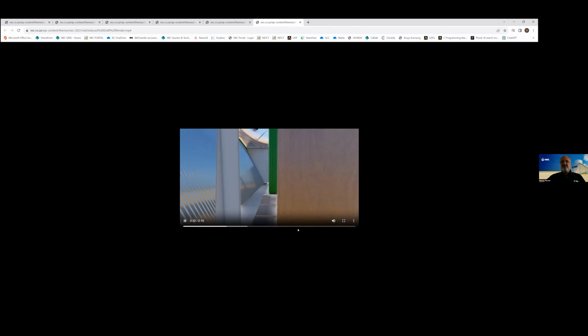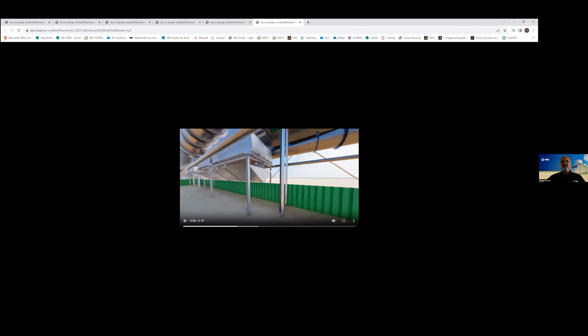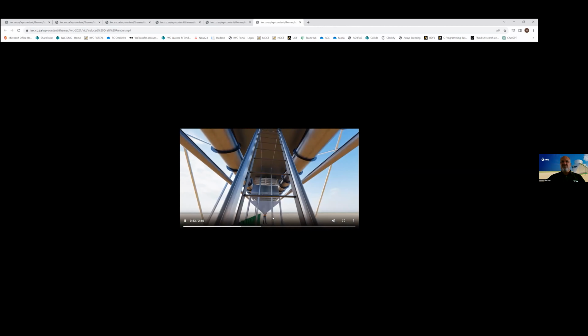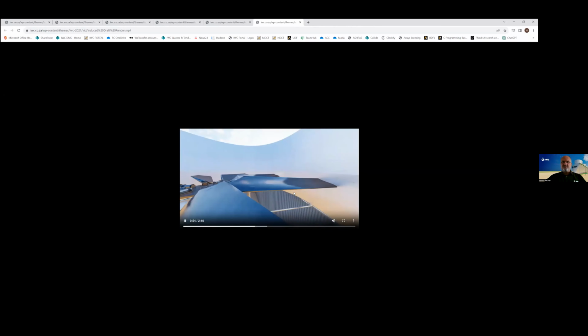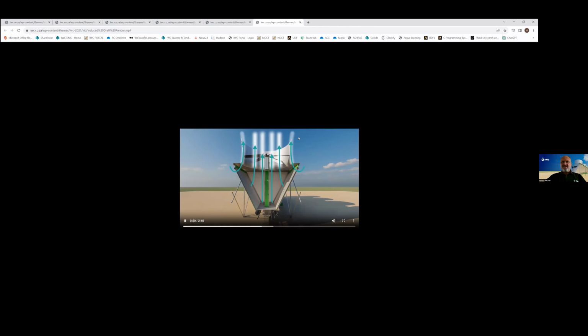Here in the floor, you see these gratings, so to speak. This is where we put in a booster system called the hybrid dephlegmator, and you'll see it underneath. I'll tell you the details just now. This is incorporated into the air-cooled condenser, and it has the impact of a supercharger for the air-cooled condenser. So it's an evaporative system to enhance the performance dramatically. Then also the system of ours has a fan stack with a diffuser, which allows for improved fan efficiency, all enhancing performance. Here you see the streamlines as the air flows through the system.